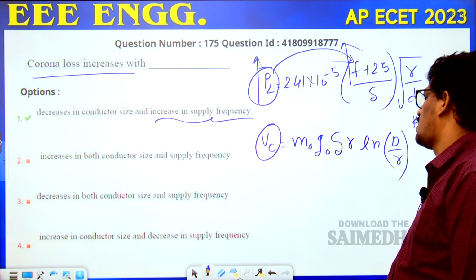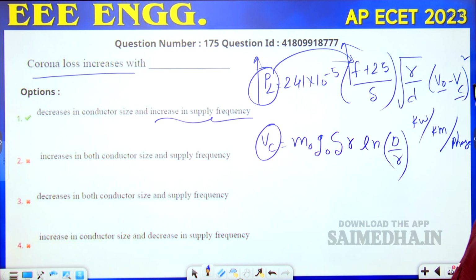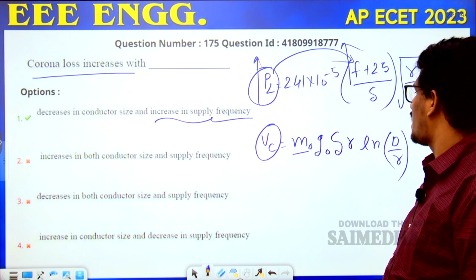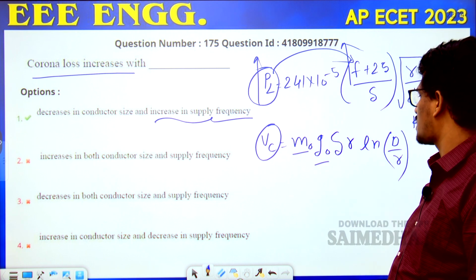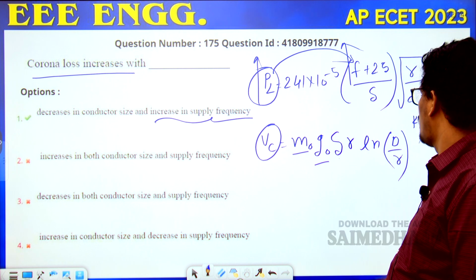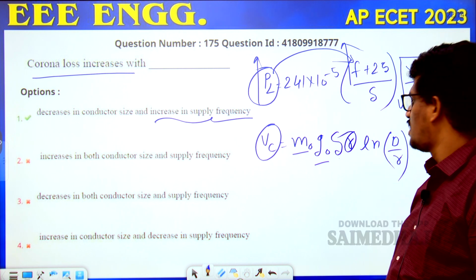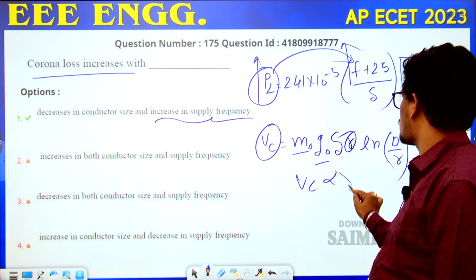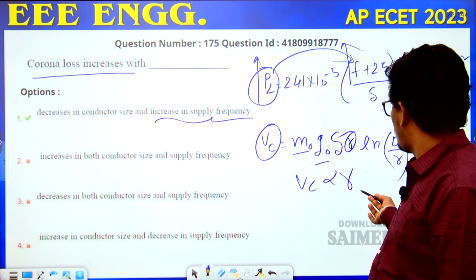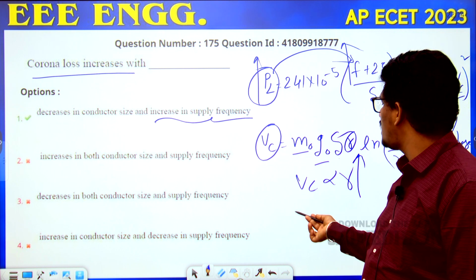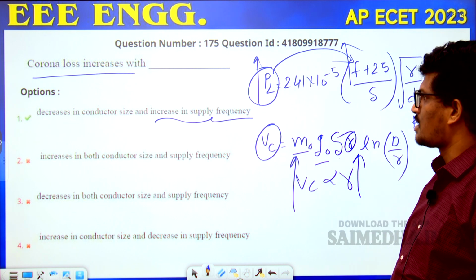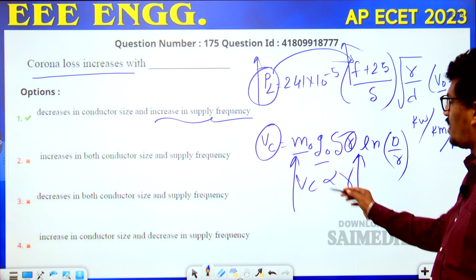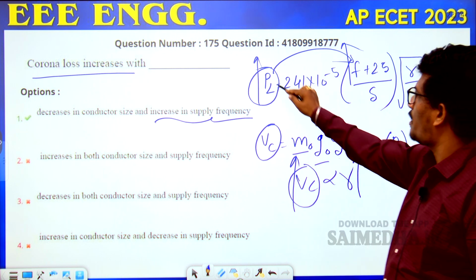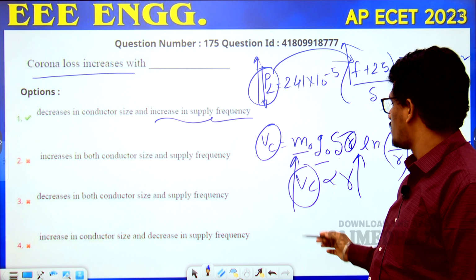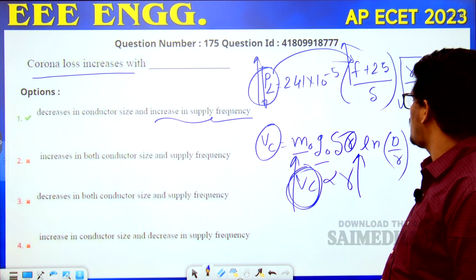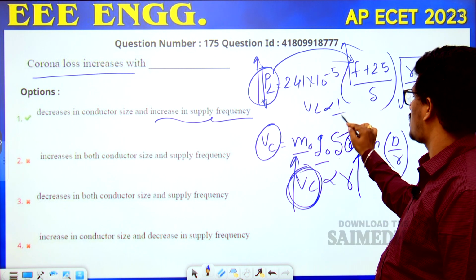This is the formula for critical disruptive voltage. Here M0 is the irregularity factor, G0 is the air dielectric strength, delta is the air density, and R is the radius of the conductor. Critical disruptive voltage is directly proportional to the radius of the conductor. As the radius of the conductor increases, the critical disruptive voltage also increases. Whenever the critical disruptive voltage increases, the power loss due to corona decreases. Simply, the relation between the critical disruptive voltage and power loss is inversely proportional.